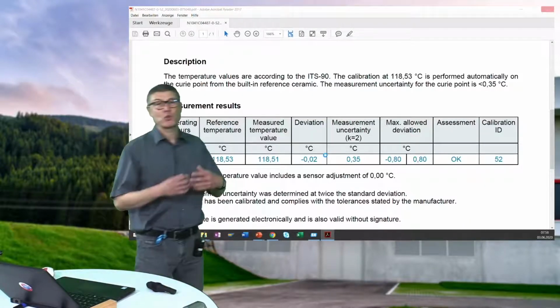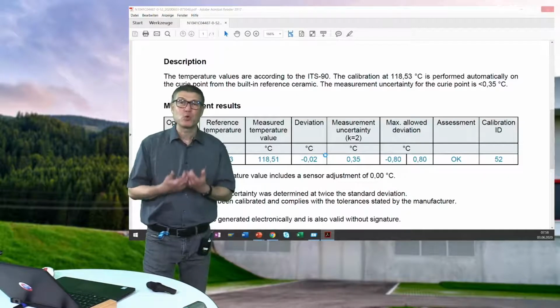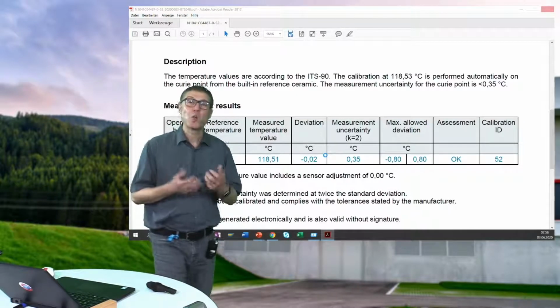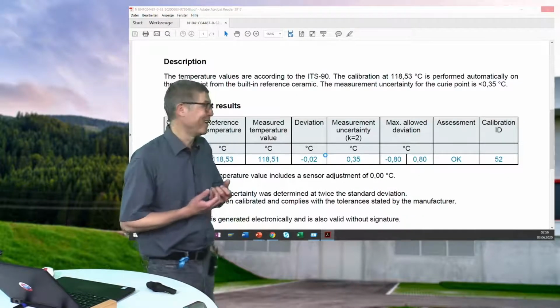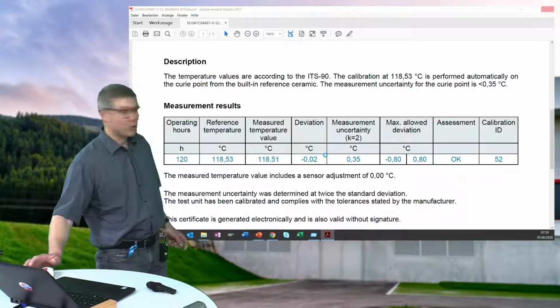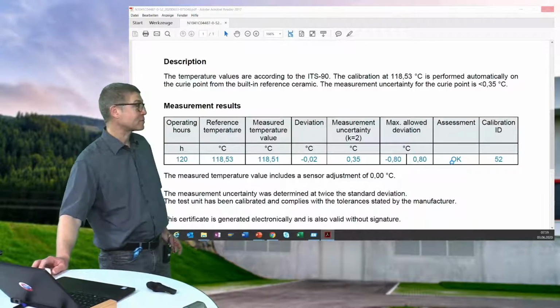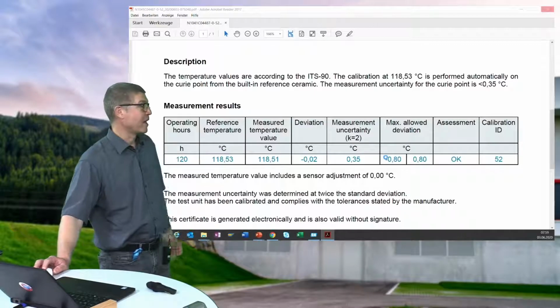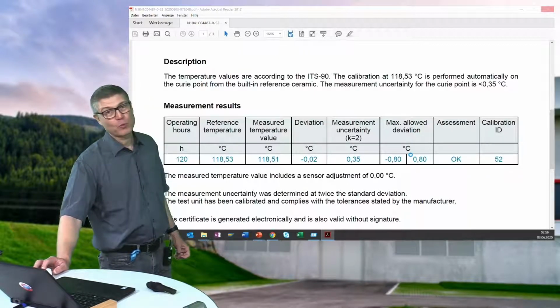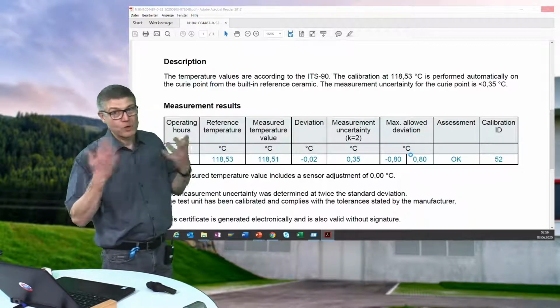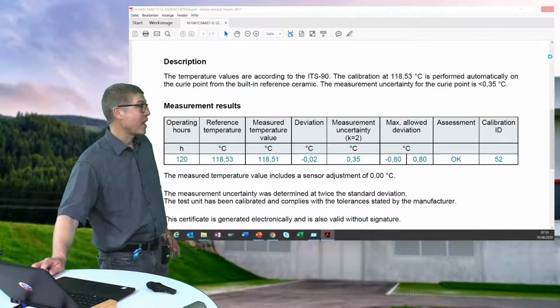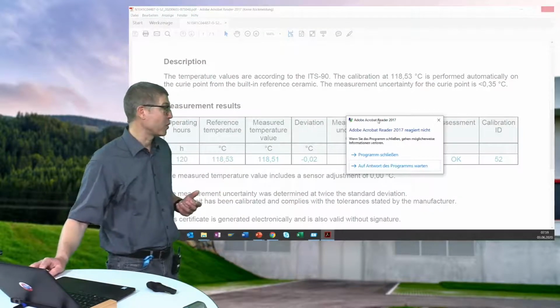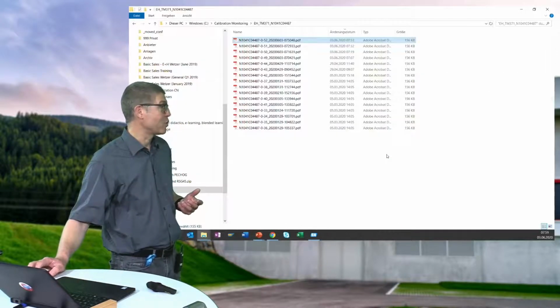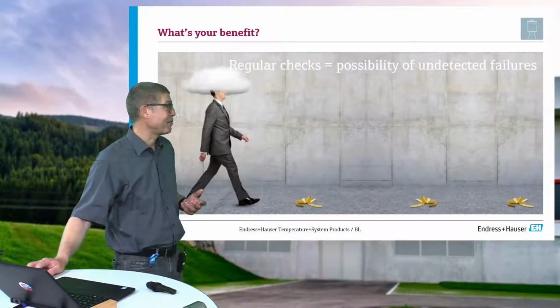So we have a deviation of 0.02 degrees Celsius, which is in fact good, really good. So the calibration result is fine, because in this case, the allowed deviation would be 0.8. You can surely adjust this value. So, and this certificate is produced every time you pass this temperature. That is the general idea, and now I will shut this PDF reader.